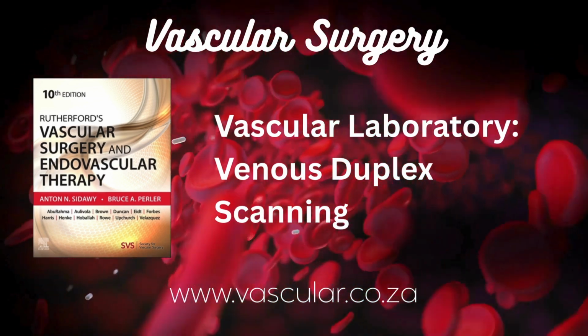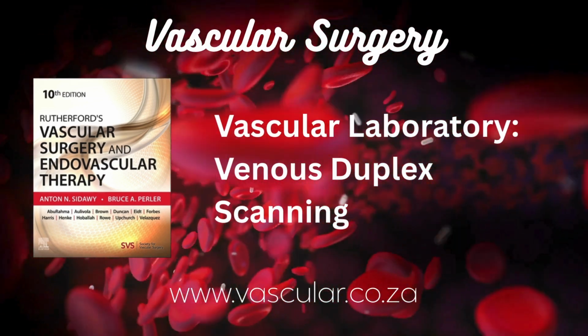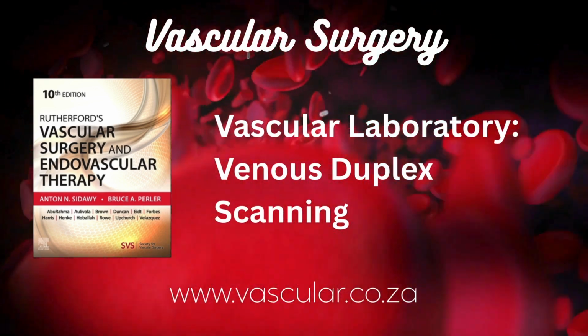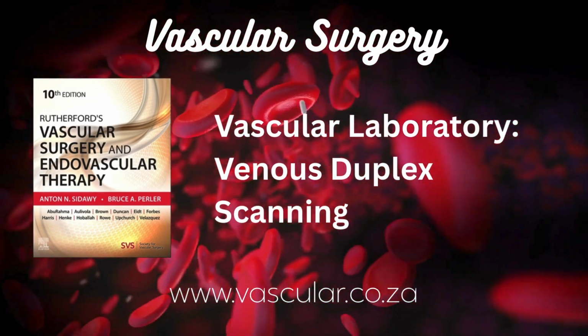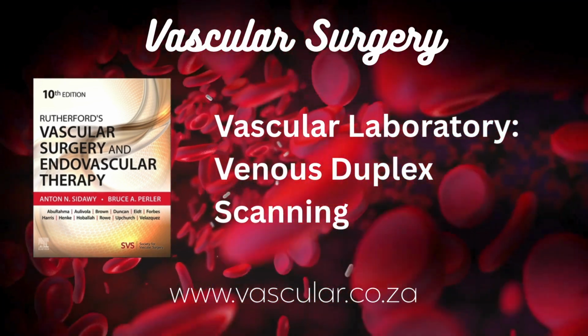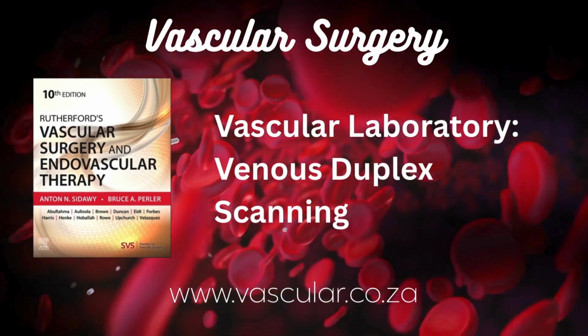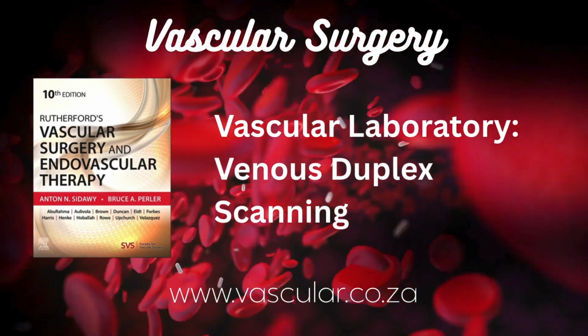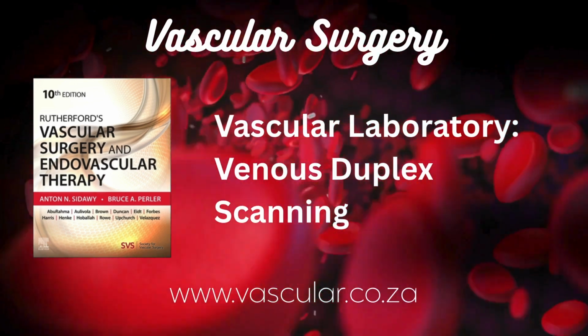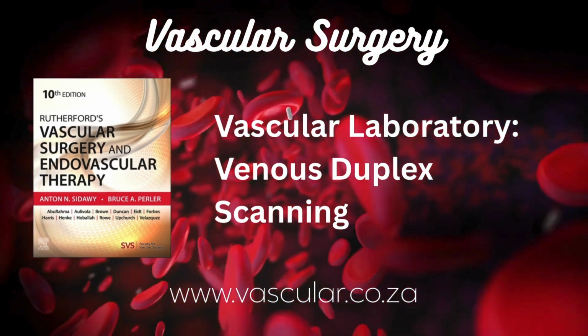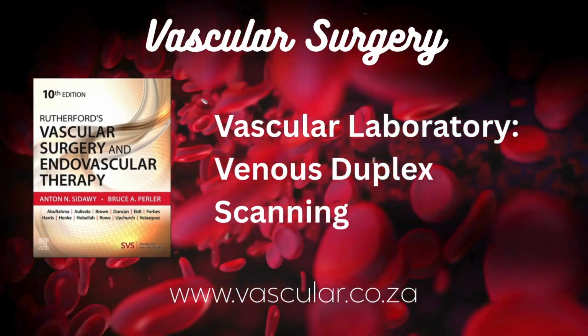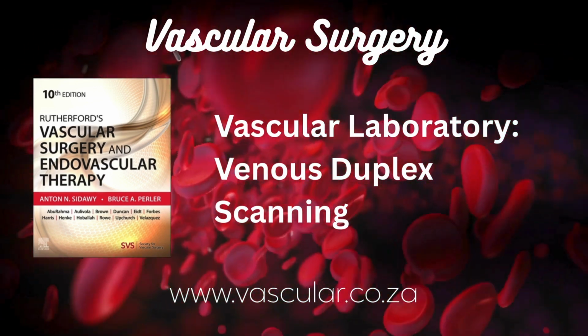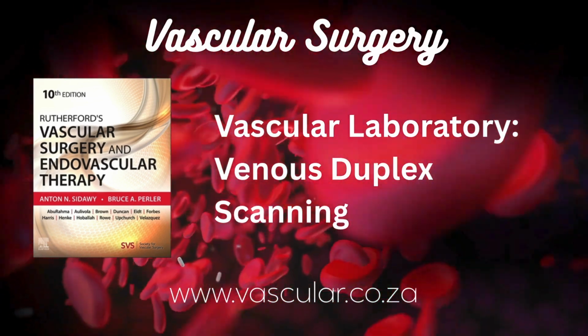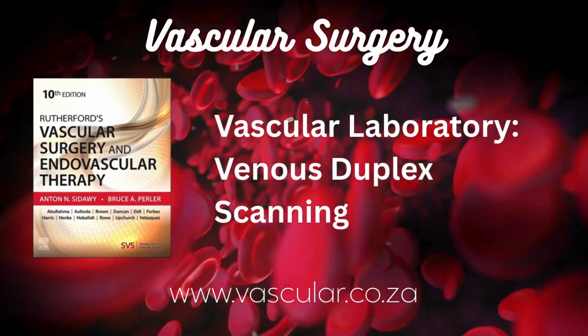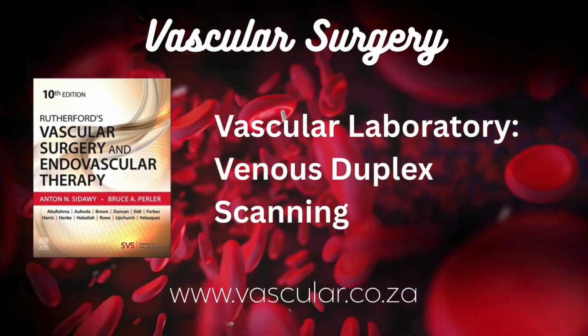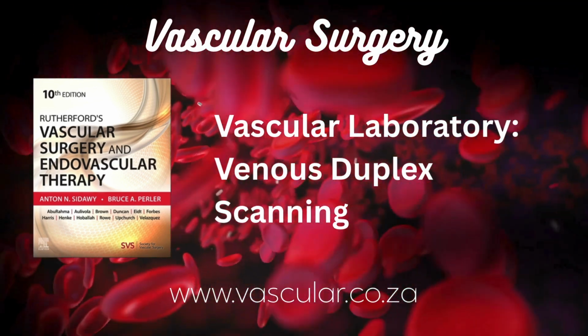Okay, the essential equipment includes a duplex ultrasound machine, and it has to have color flow Doppler capability. Color flow. Yeah, it shows the direction of blood flow using color. The machine also needs specific imaging and Doppler frequencies appropriate for visualizing the particular veins being examined, deep or superficial. And spectral Doppler is crucial too. This lets the operator precisely focus on the blood flow in a tiny area and measure its speed and direction accurately. Think of it like zooming in on the flow. Okay. And of course, the machine needs to clearly display and permanently record both the ultrasound images and those Doppler waveforms. So definitely more sophisticated than a basic ultrasound machine.